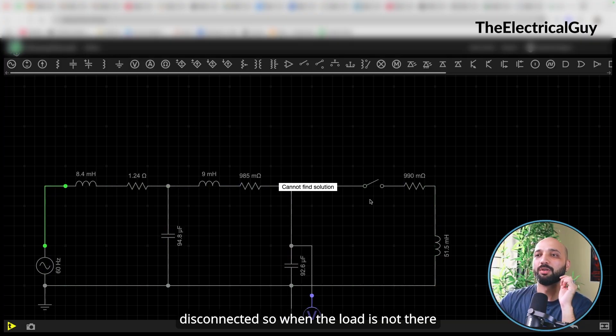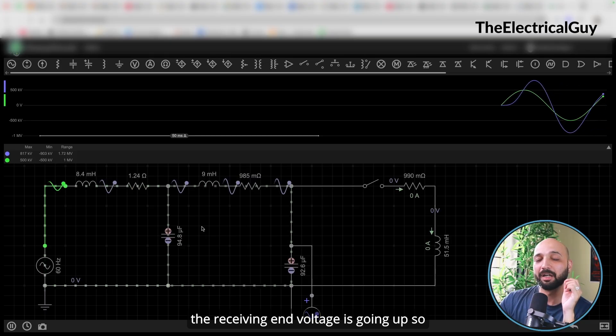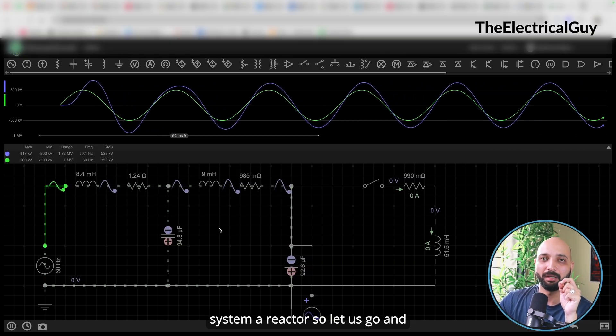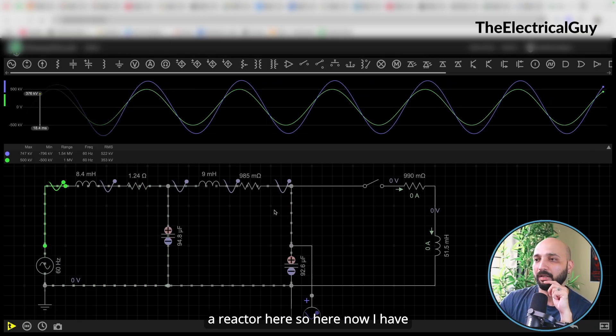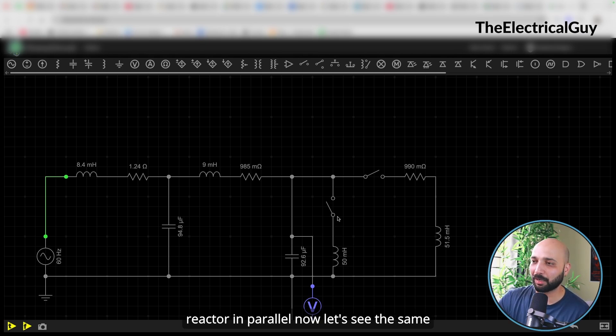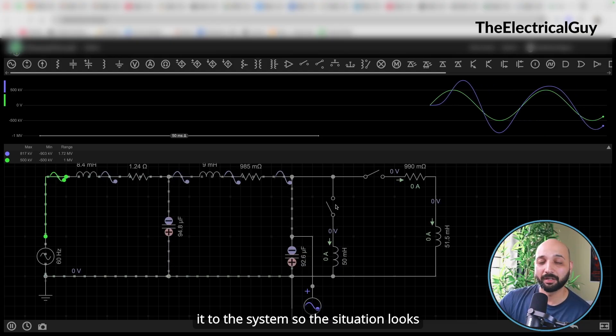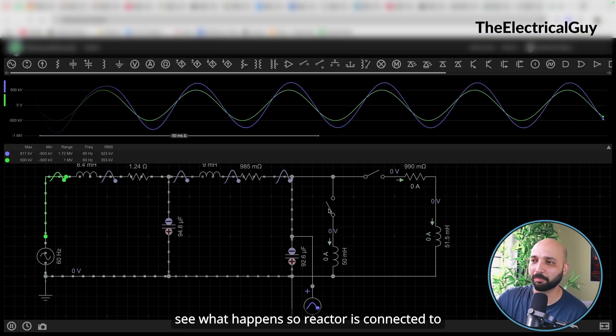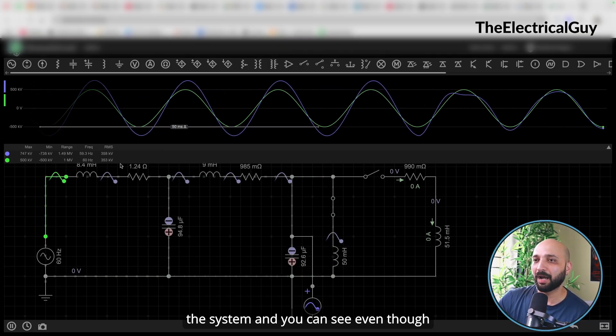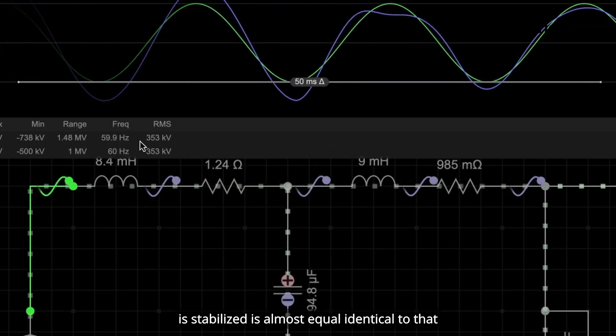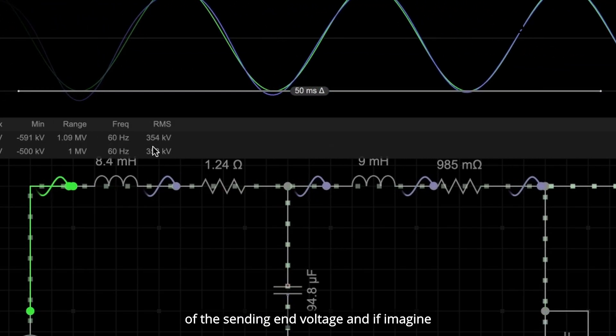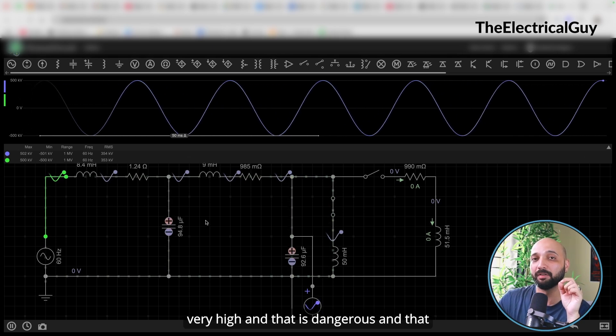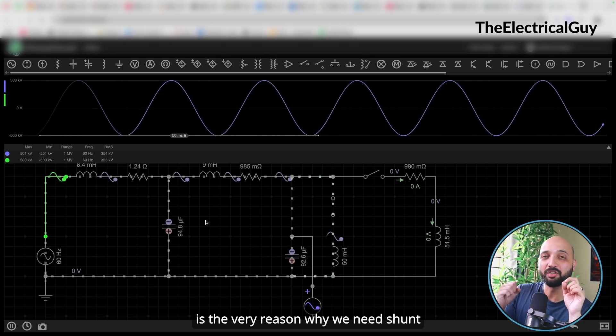The problem is when the load is disconnected — the receiving end voltage goes up. To solve this, as discussed in the theory, we need to add a reactor. So I am going to add a shunt reactor here in parallel. With the load still disconnected, I now connect the reactor to the system — and you can see that even though the load is not connected, the receiving end voltage is stabilized and almost identical to the sending end voltage. Without this reactor the receiving end voltage would be very high, and that is dangerous. That is the very reason why we need shunt reactors in the system.